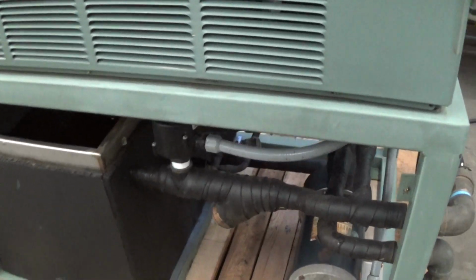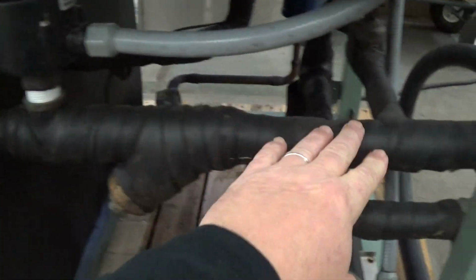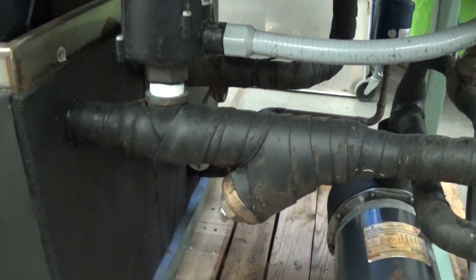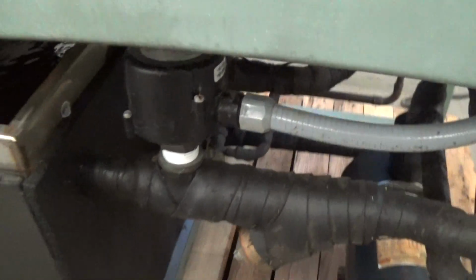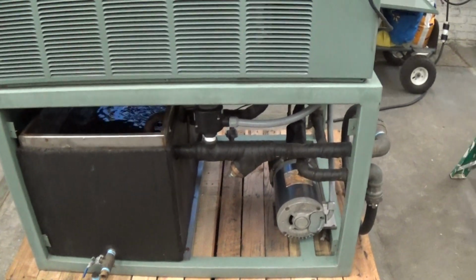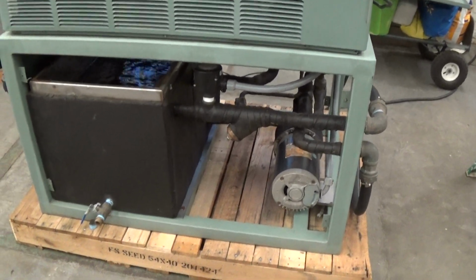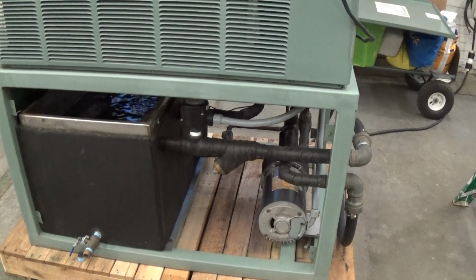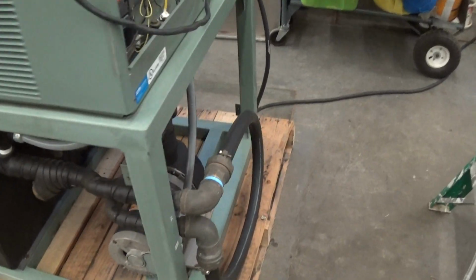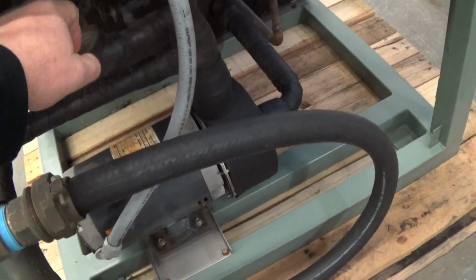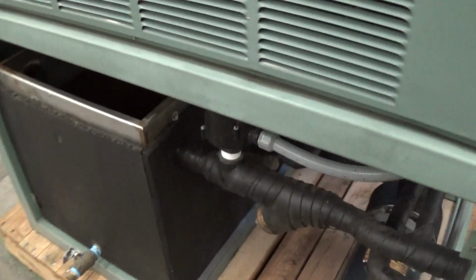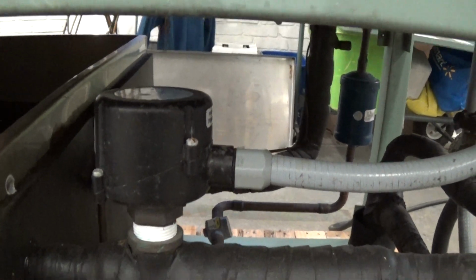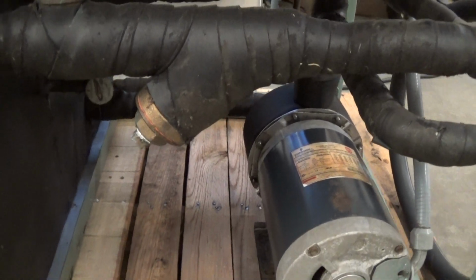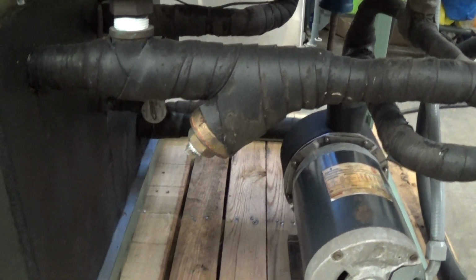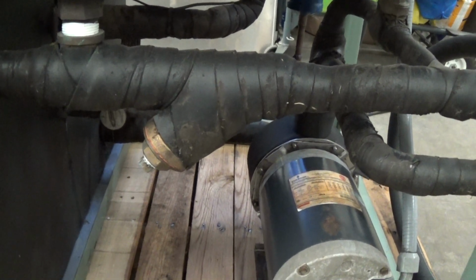An example of adjusting that more open, if you will, is if our flow switch, which is here, which is the return coming back to the chiller, is not satisfied. An example of that would be if your process has solenoid valves on the inlet to your machines, and they're all closed. And if you don't have enough flow coming back to the chiller, then we'll want to open up this bypass a little bit more so that your flow switch right here is satisfied. This here is important. This is a Y strainer. You take this out, check the mesh. It's more or less a filter. That's something you want to do regularly.